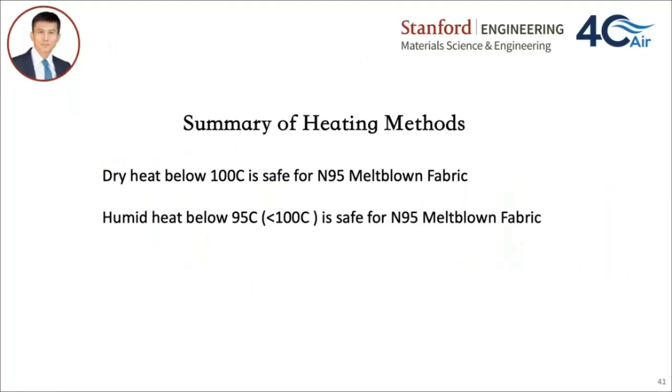So in summary, the heating method looks very promising. Dry heat below 100 degrees Celsius is safe for N95 melt-blown fabric. But be cautious. What you need to be careful about is, of course, the strap, the elasticity; you need to test that out. We tested some temperatures already, and they look good. The final conclusion will be coming in a few weeks. And humid heat can be done below 95 degrees Celsius, I say roughly. But if it's 100 degrees Celsius steam, it looks like after 3 cycles it can damage your filtration efficiency.